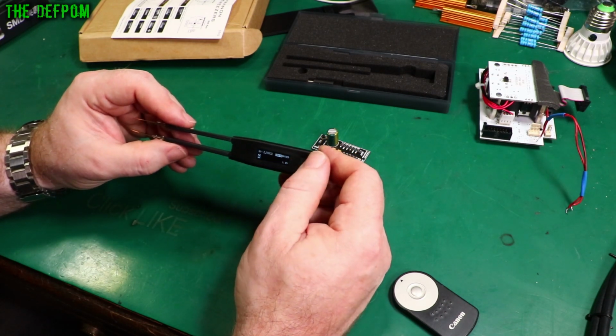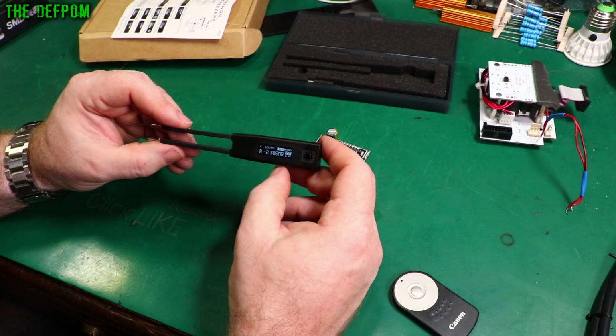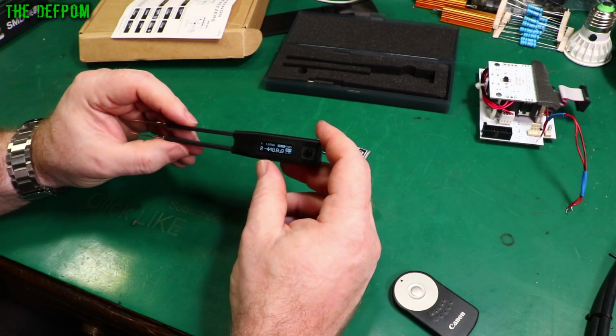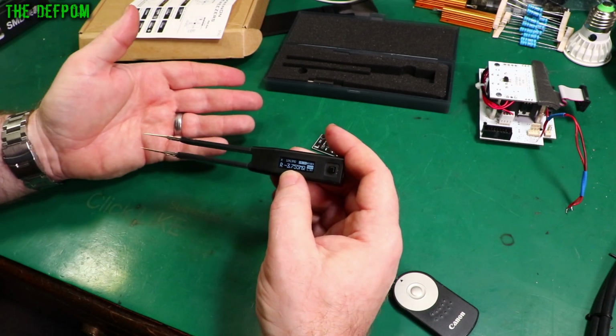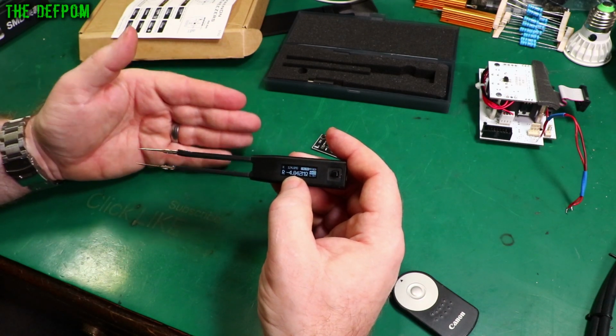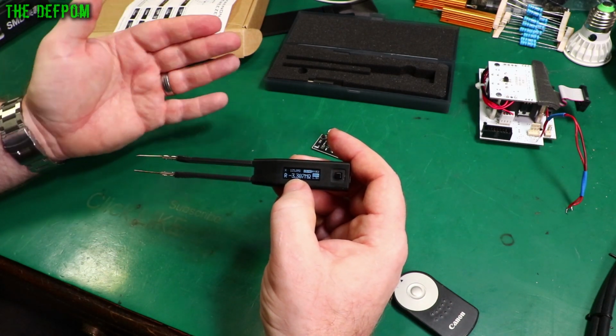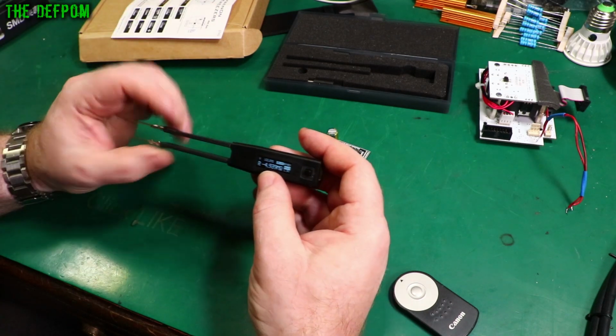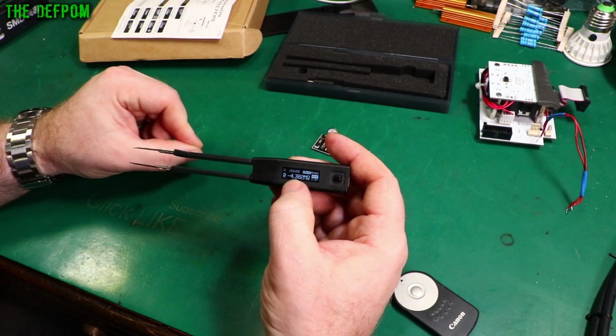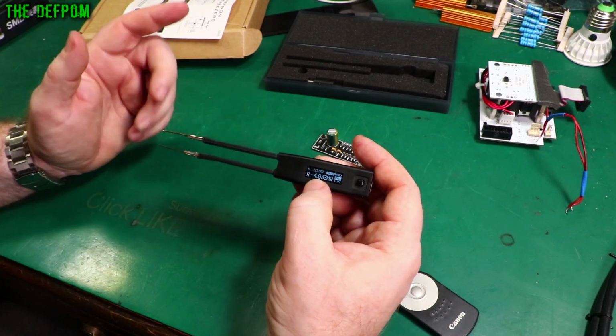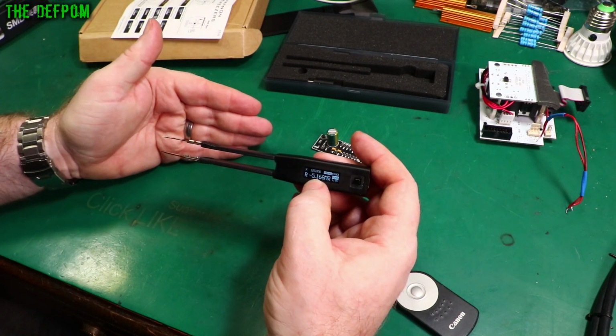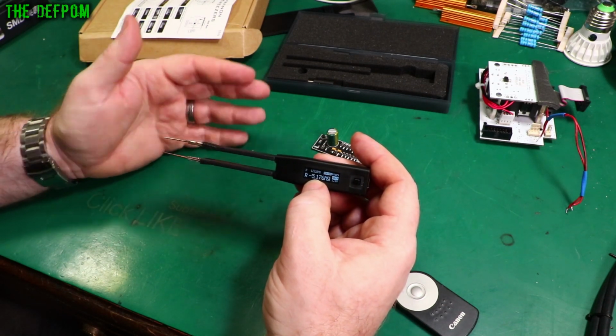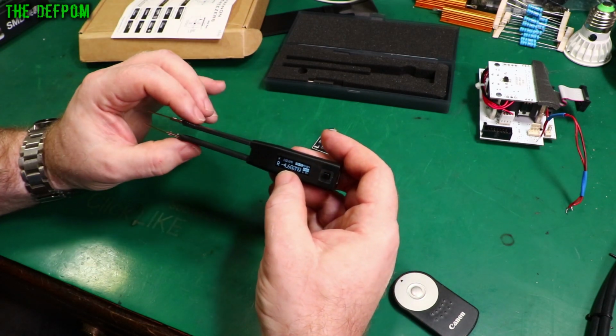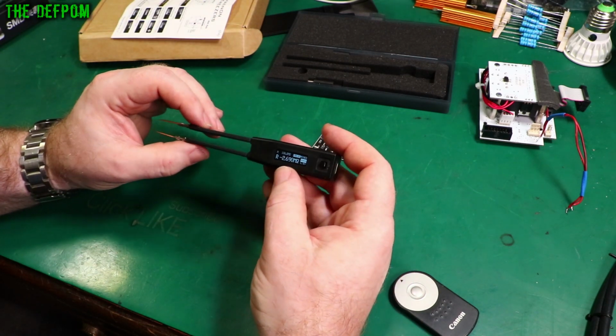So anyway, I went into this resistance mode in this one here, and this one was working fine. So it measured with a 200 milliohm offset based on my calibrator, because that's the lead resistance and the resistance for the calibrator and sort of stuff. So if I shorted the leads directly on the input to the calibrator, it was like 17 milliohms. That's lead resistance. So lead resistance is 17 milliohm. I've got like 200 milliohms for the calibrator. So that was out by about 200 milliohms, and I was doing those measurements.